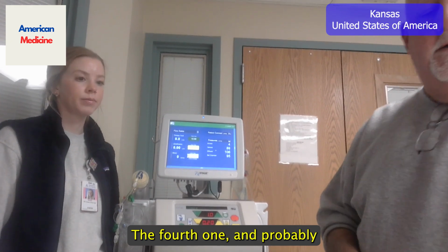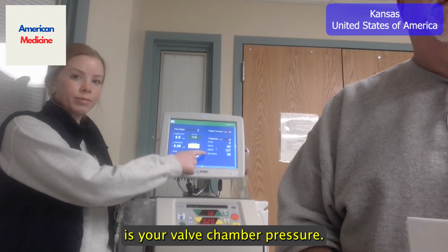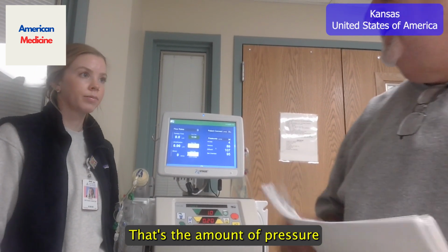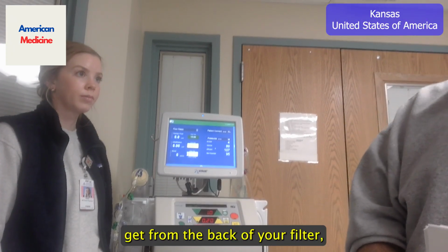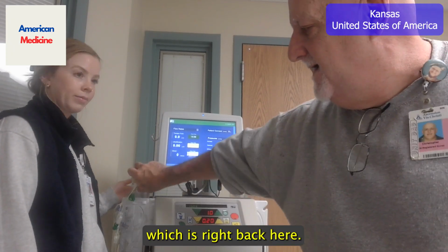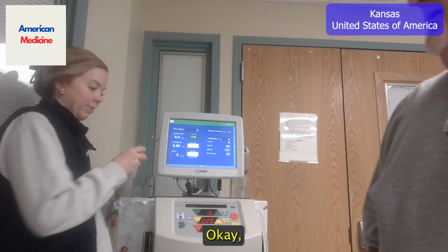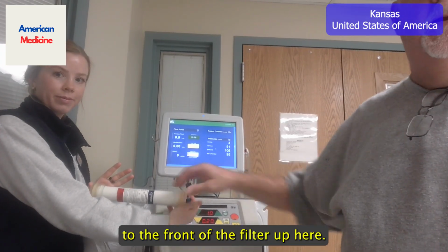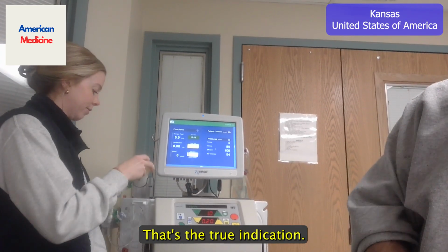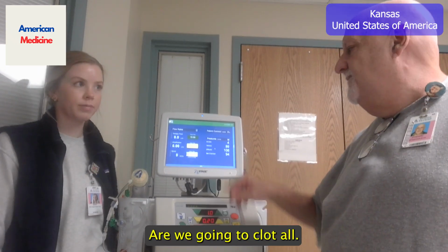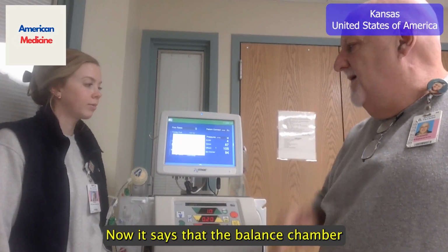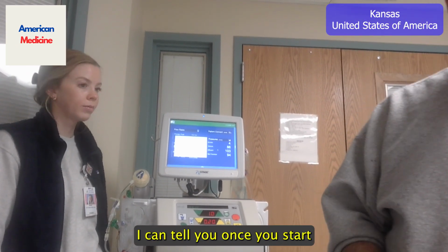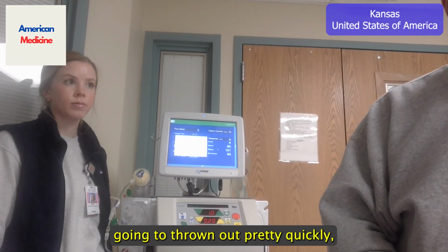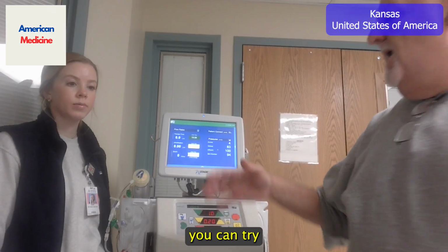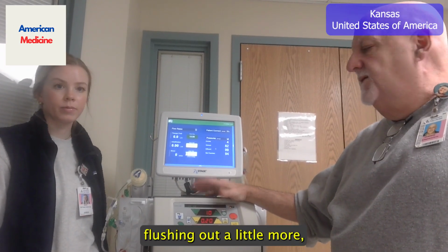The fourth one, and probably your most important one, is your balance chamber pressure. That's the amount of pressure it takes to get from the back of your filter, which is right back here, to the front of the filter up here. That's the true indication: are we going to clog, or are we going to clot off? Now it says that the balance chamber should be less than 600. I can tell you once you start getting in the 500 range, your machine's going to clot off pretty quickly. You could try flushing it a little more, see if that works.